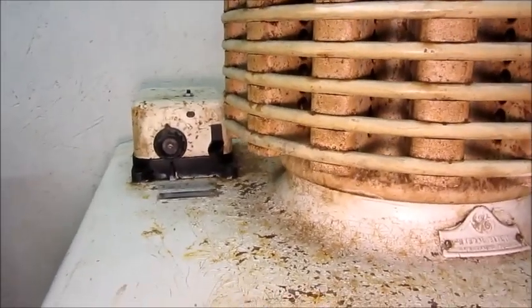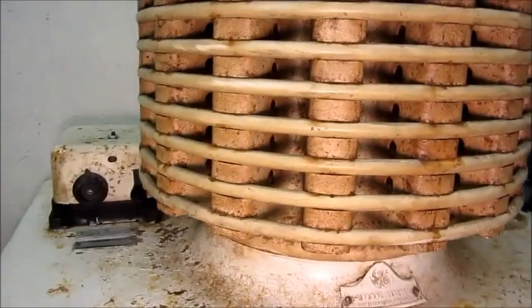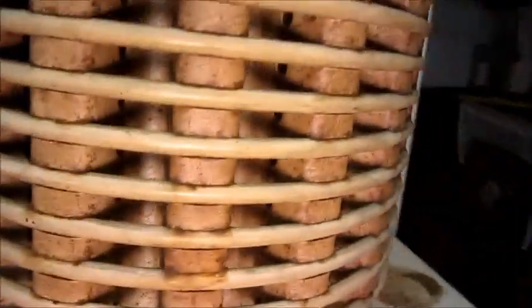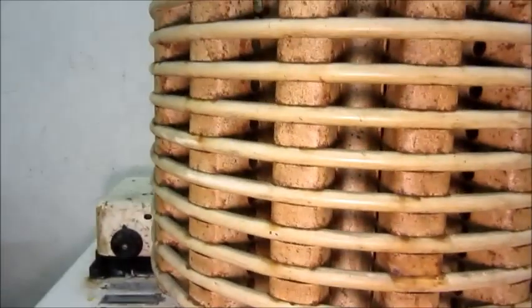All right, it's been a few minutes. It's gotten slightly louder — nothing I would call alarming. There's just a little bit of heat in the coils and a little tiny bit in the dome. We're already down to about five degrees or maybe ten, so it looks like everything's going well at this point.